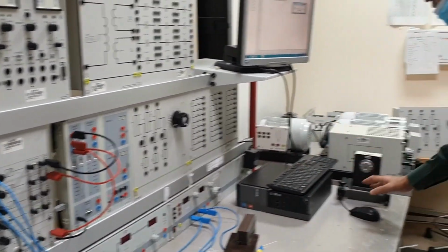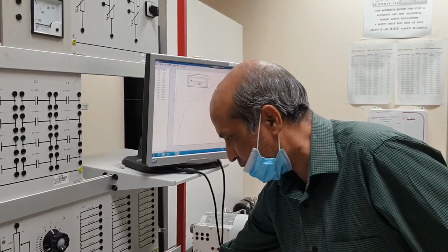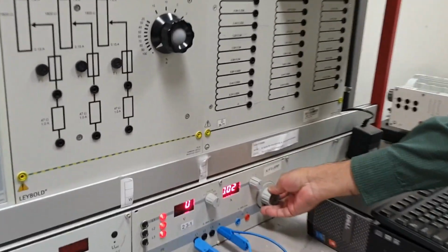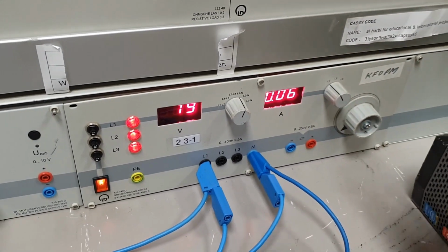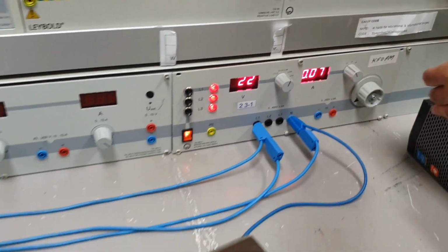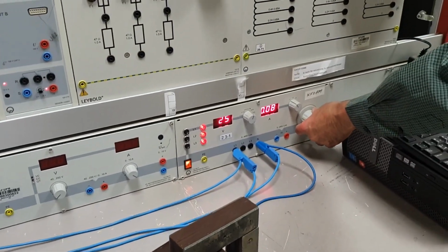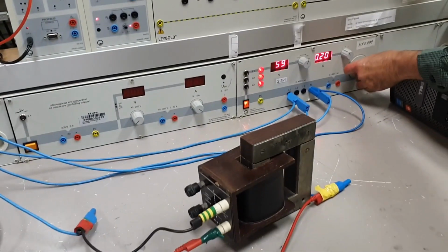So we increase the voltage by 10, we switch on the power supply. This is where you can control the voltage. So we have 0, and we have 10 and 20 like that, and with every reading we are going to press F9 or the clock in manual recording, and we will get the whole curve. So you go maximum up to 160 volts.